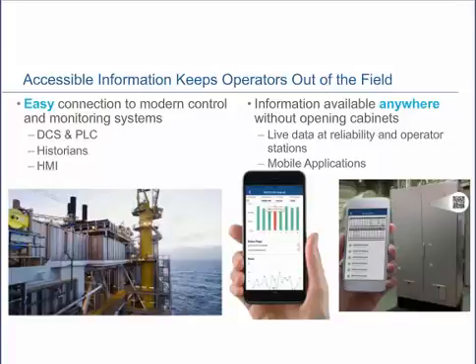And also you have Modbus RTU and Modbus TCP. So that's been available for some time in most of the systems that they're able to pull that data out. Basically, you've got registers that are assigned to where your values are going to be located so that someone who wants to get that data can now map a connection to that particular register and pull that data in. So getting data out of the system is very easy.